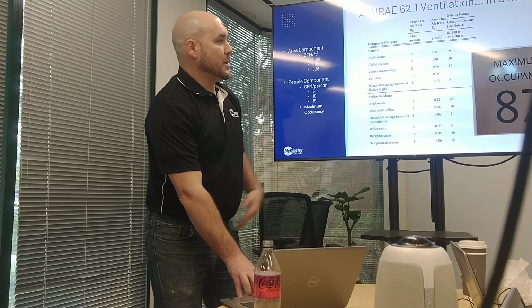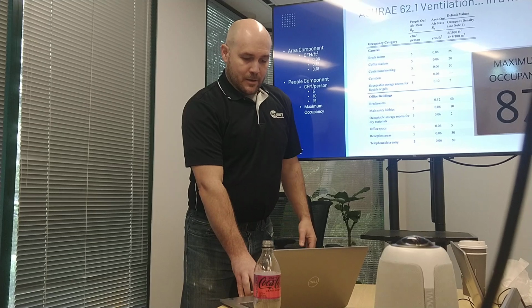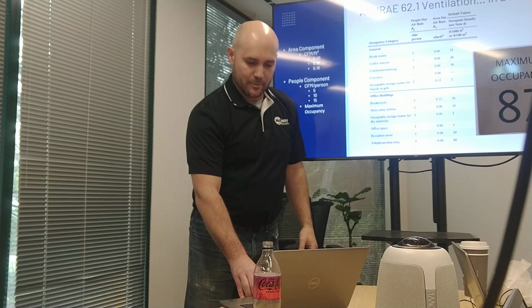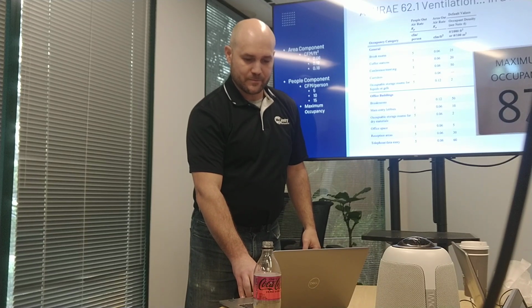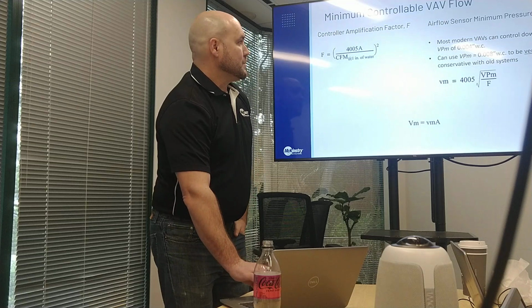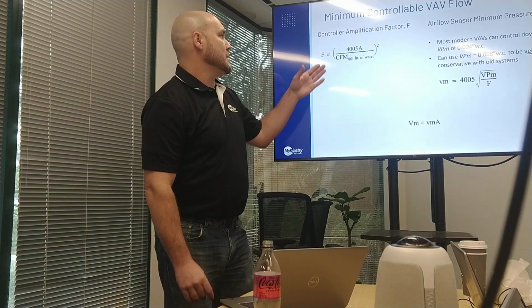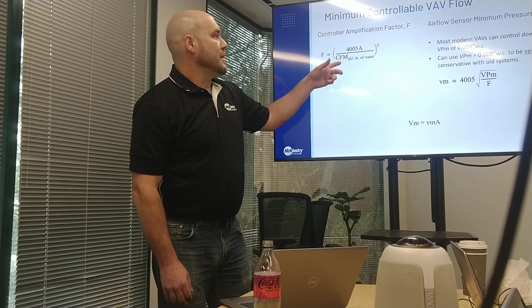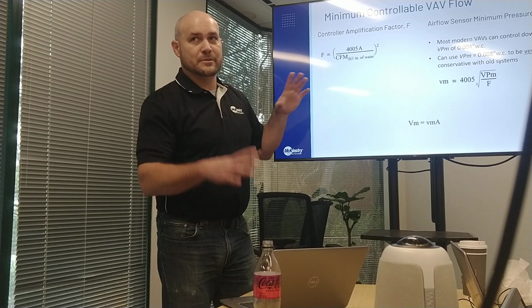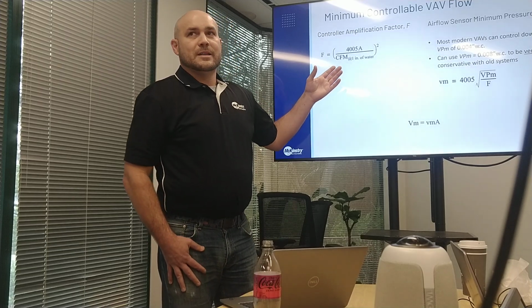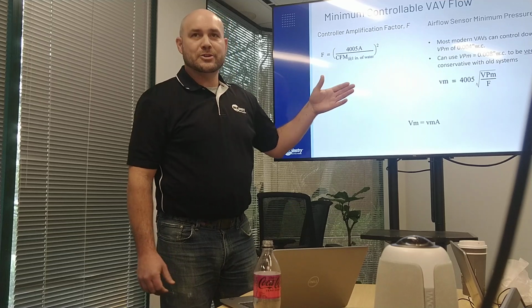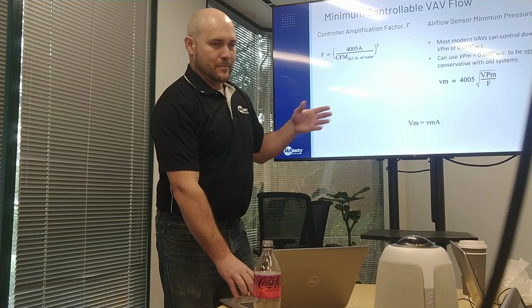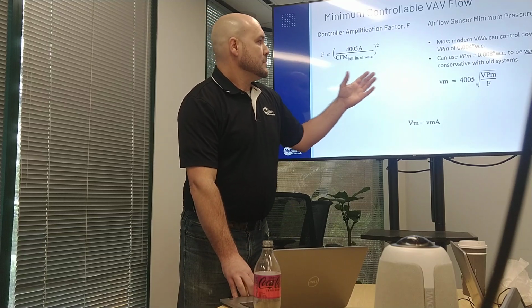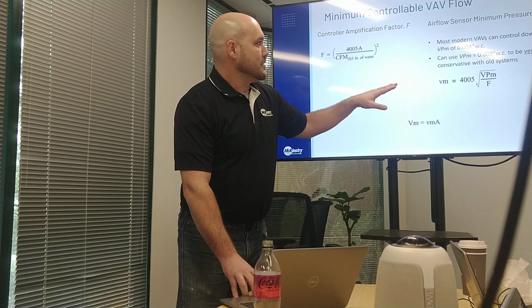Excuse me. But yeah, this kind of trumped in terms of the people. Rather than just saying, 50 CFM per 1,000 square feet, that's great. Well, 87 is a far more justifiable, defensible kind of number, if you can snap a quick picture of that. Here's showing some of the equations that go into this, the amplification factor, and the input that we need to capture from a VAV box, which is usually on the sticker on the side, is that box's CFM at 1 inch of water column pressure drop. We'll show you on the next slide what that can look like.